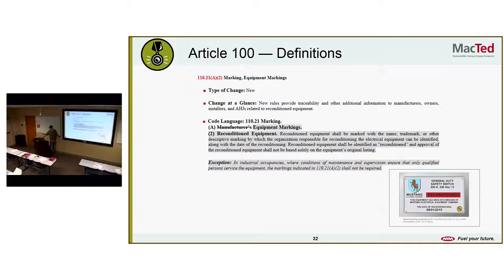Marking, equipment markings, type of change, new. New rules provide traceability and other additional information to manufacturers, owners, installers, and authorities having jurisdiction related to reconditioned equipment. So this might have to do with what you were asking there, Josh. Reconditioned equipment shall be marked with the name, trademark, or other descriptive marking by which the organization responsible for reconditioning the electrical equipment can be identified, along with the date of the reconditioning. So that doesn't say specifically what, but I could see that applying to motors. So look for those coming.